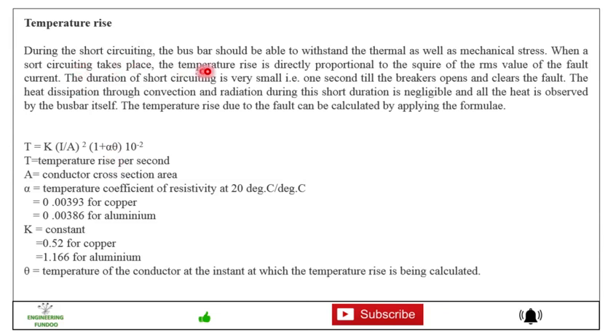So during the short circuit test, the busbar should be able to withstand the thermal as well as mechanical stresses. When short circuiting takes place, the temperature rises directly proportional to the square of the RMS value of the fault current. The duration of short circuiting is very small, one second till the breaker opens and clears the fault. The heat dissipation through the convection and radiation during this short duration is negligible and all the heat is absorbed by the busbar itself.